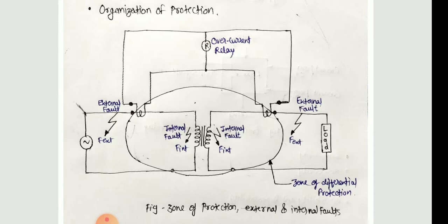How far the zone is crisply carved out depends upon the relaying principle used. In general, it can be said that the differential relaying gives a much more crisply carved out zone than overcurrent or distance relaying.